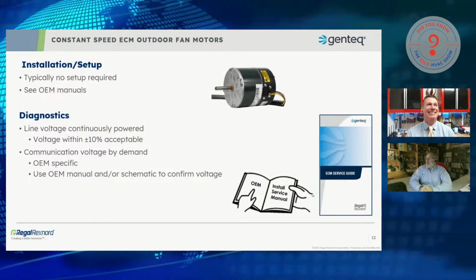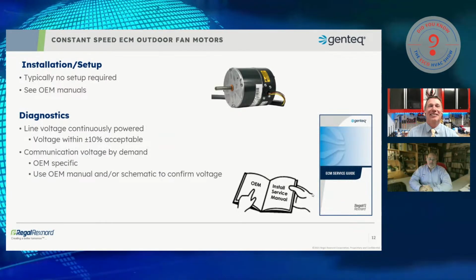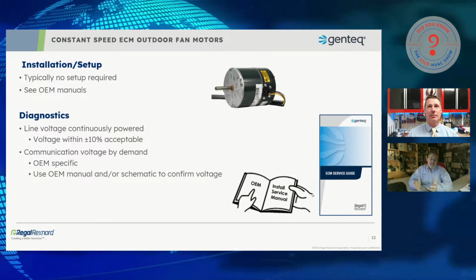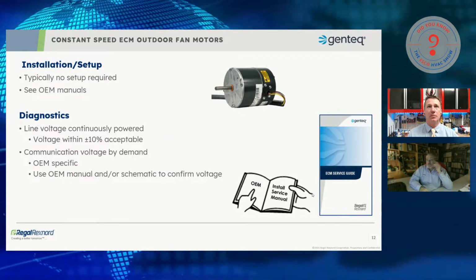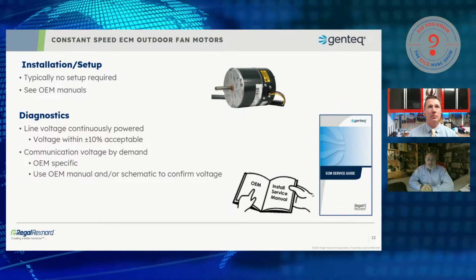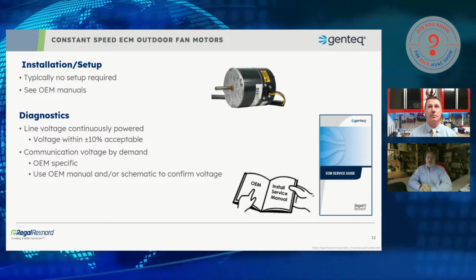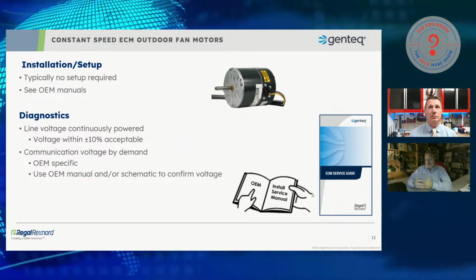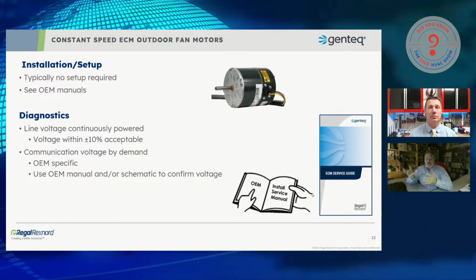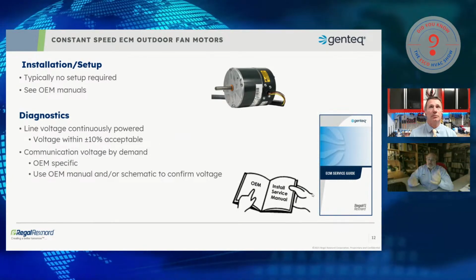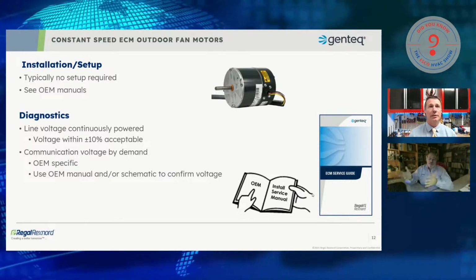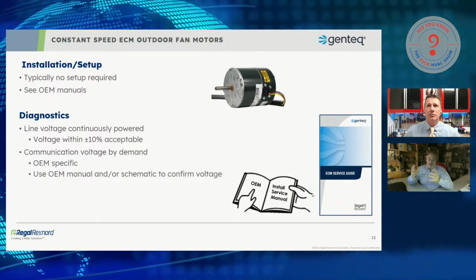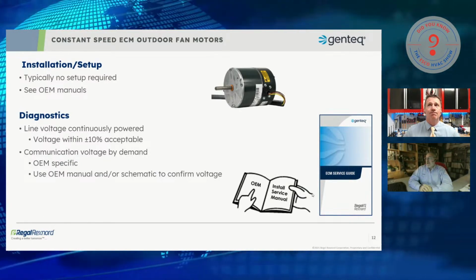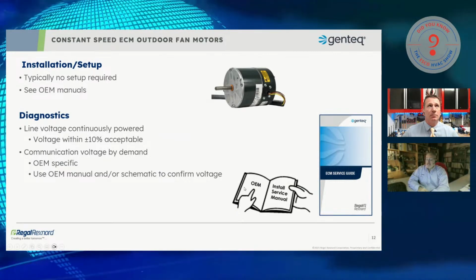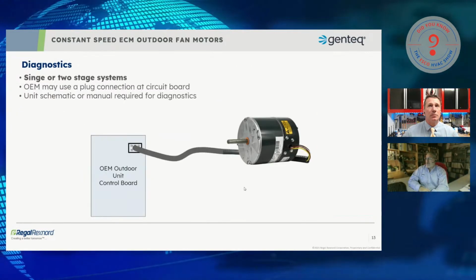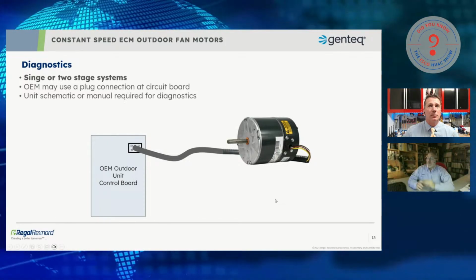So there you go. So we're going to go right into installation setup and diagnostics. Okay. Installation setup is really easy. There isn't any. The board comes set up with the motor for either 1-speed, 2-speed, or the low ambient 3-speed operation. Unlike the indoor blower motors, where we have to select the correct heating speed for temperature rise and cooling speed for CFM, those speeds, those torque values or CFM values, could change based on the static pressure of the system. We don't have those influences, right? We don't have ductwork on either side of the condensing unit, so we don't have to worry about that. It comes basically pre-set up from the factory. So let's talk about diagnostics. Diagnostics are going to be what you just said. It's going to be line voltage and low voltage. So we'll start off with the single or, before I start.